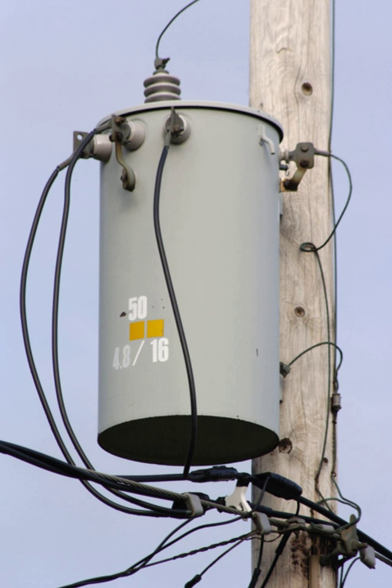Primary distribution lines carry this medium voltage power to distribution transformers located near the customer's premises. Distribution transformers again lower the voltage to the utilization voltage used by lighting, industrial equipment or household appliances. Often several customers are supplied from one transformer through secondary distribution lines. Commercial and residential customers are connected to the secondary distribution lines through service drops. Customers demanding a much larger amount of power may be connected directly to the primary distribution level or the subtransmission level.